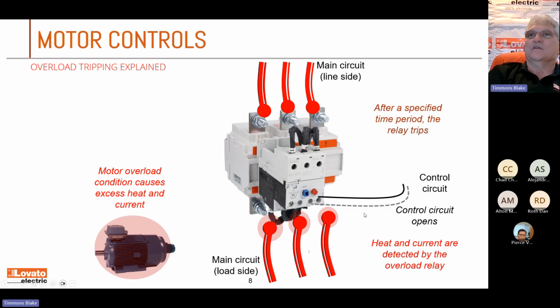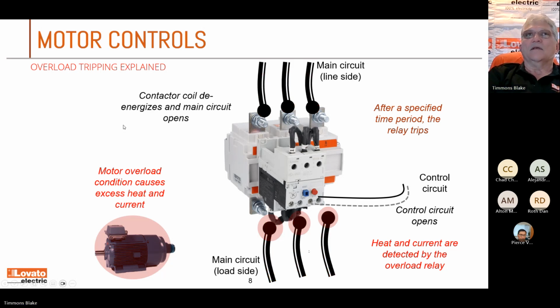It trips. So it turns off the control circuit to the coil of the contactor. So the contactor drops out. So the only real switching you get in an overload is just that little control circuit. And it controls the switching of the contactor, which is made for the heavy duty switching. Okay. And it turns off.